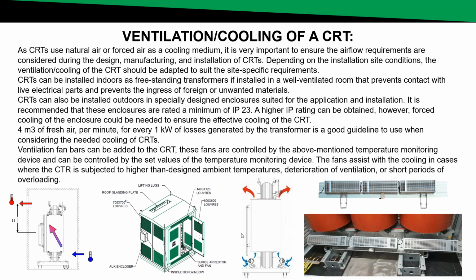The next picture is just a typical example of the operation of the fans. So you can see the fans are mounted at the bottom, usually on the HV and on the LV side of the winding. And cold air is then forced through the transformer to try and get rid of excess heat build-up during high ambient temperatures or short periods of overload. This is a typical example of what a fan bar looks like. And this is a typical installation of fan bars on cast resin transformers.